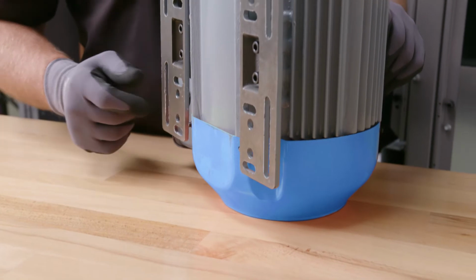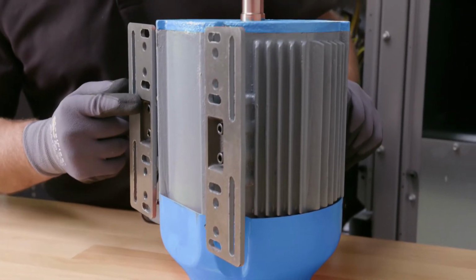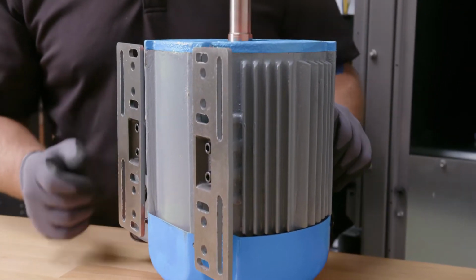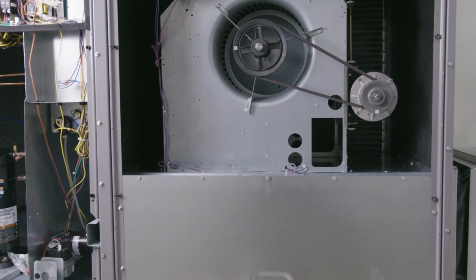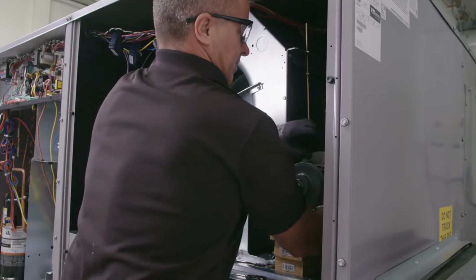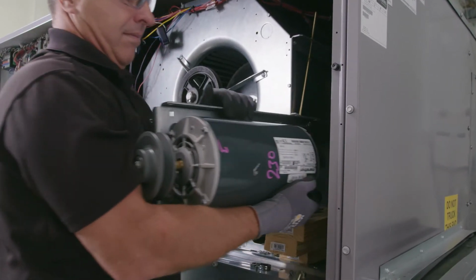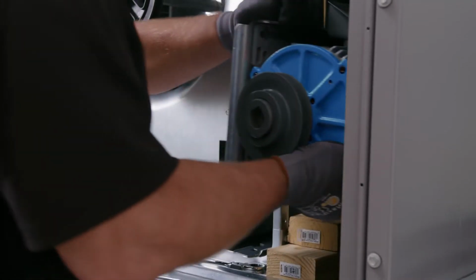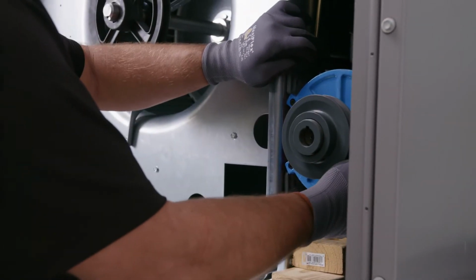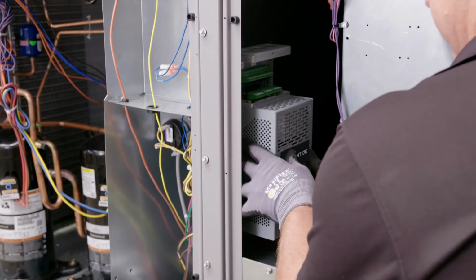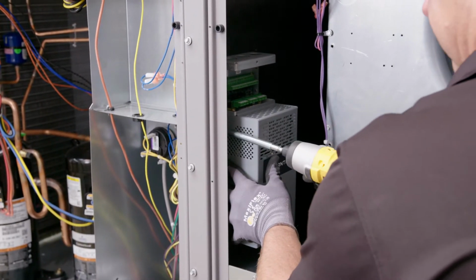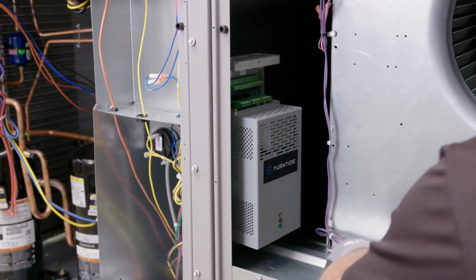termination. Before starting, please note that if you are rigid mounting the motor, you may need to attach the feet. This requires a metric Allen wrench. Replace the existing motor with the new smart motor. Next, mount the motor controller inside the RTU blower cabinet, or in another approved location per the installation documents.